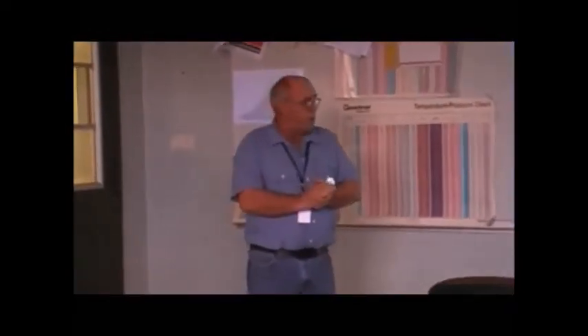We look down at the bottom and we see that we can break it down into the different parts that we figured. We can get the percentages of the heat loss and heat gains. But the bottom line is this equipment must be able to service those numbers. Okay? When you do the room by room, you may say, hey, that's not exactly the same. But keep in mind, this takes in duct losses and other problems that are truly associated with a load calculation for a building or a home. That concludes our block load.